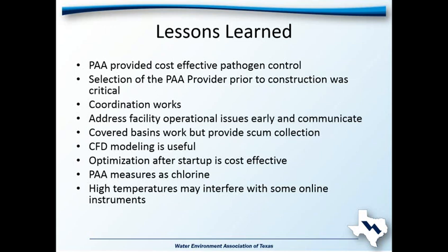And we did find that with our high temperatures, the water can get as high as 105 degrees in the effluent leaving the plant, that it was interfering with some of our online instruments measuring the peracetic acid.